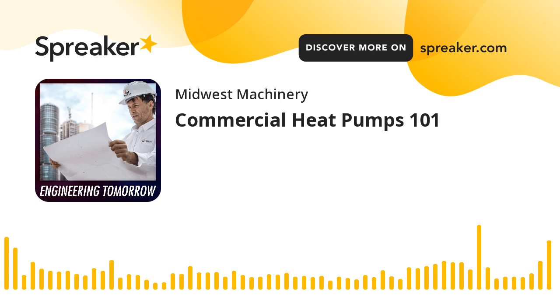But what you're saying when you do that is, I think every single one of my heat pumps is going to be on in cooling mode at the exact same time. And that just never happens. So typically what we suggest is you add in some multiplier for diversity. Typically what we see is a 0.8 or a 0.85. By doing that, you're saying, okay, at worst case scenario, I'll have 85% of my units on in cooling at the same time on a design day. And if you do that, you're not going to have any problems. You're going to be able to support all your heat pumps, and you're probably going to put a little bit of redundancy in anyways once you get to your plant. So if we've got 100 tons of cooling, we're going to size our plant for about 85, just to be safe.